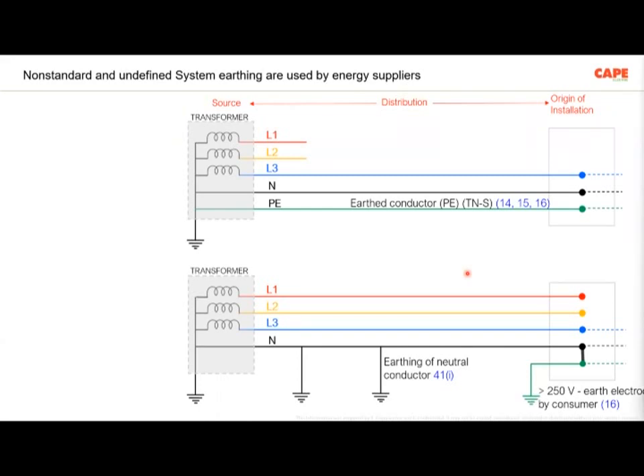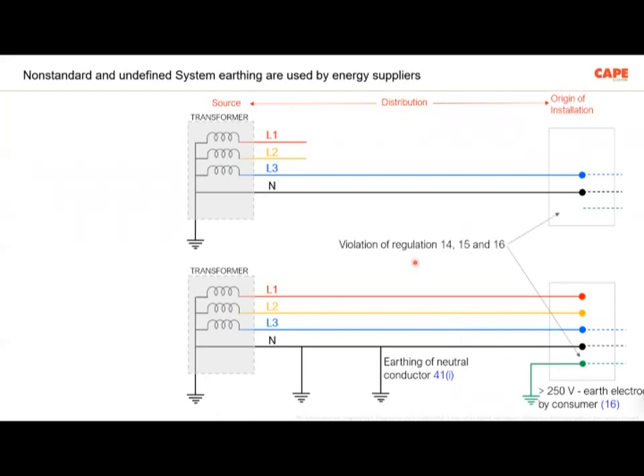But unfortunately, what happens is, one moment, let me hide this. Yeah. Unfortunately, what happens is we are supposed to get the TN-S supply, but our electricity supply company generally doesn't provide this fifth conductor. So they don't provide the link between the earth and the earthed neutral conductor.